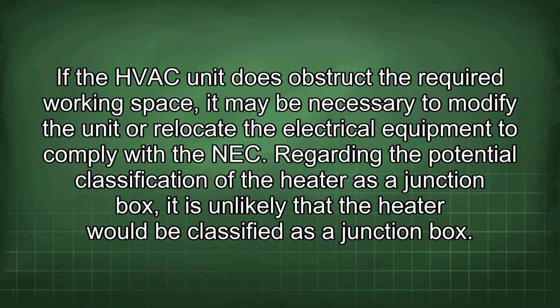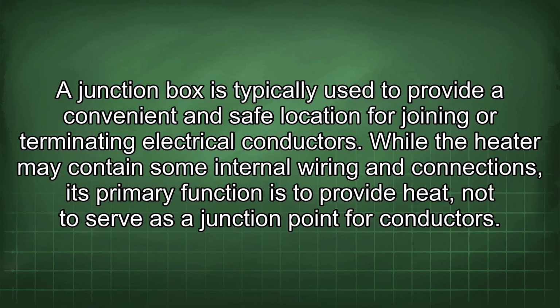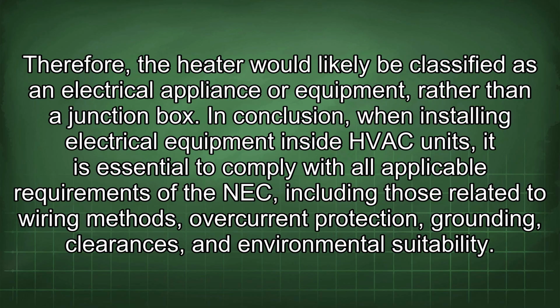Regarding the potential classification of the heater as a junction box, it is unlikely that the heater would be classified as a junction box. A junction box is typically used to provide a convenient and safe location for joining or terminating electrical conductors. While the heater may contain some internal wiring and connections, its primary function is to provide heat, not to serve as a junction point for conductors. Therefore, the heater would likely be classified as an electrical appliance or equipment rather than a junction box.